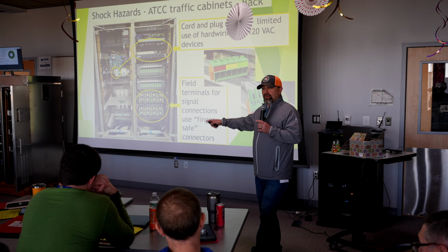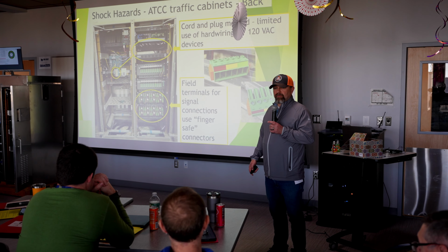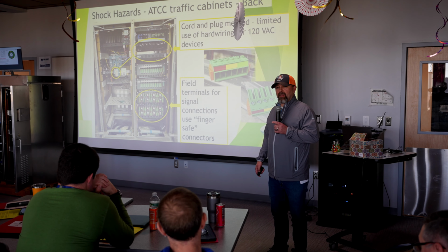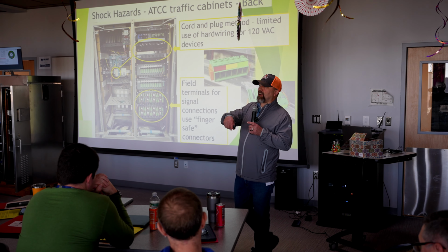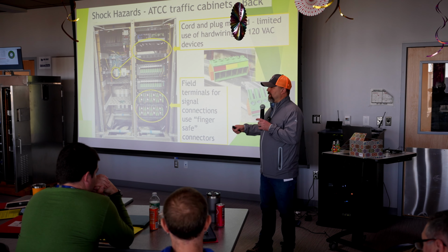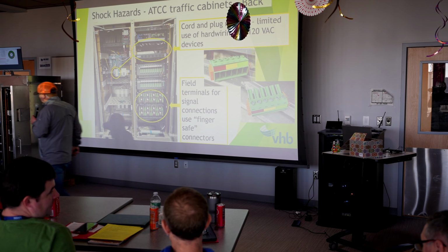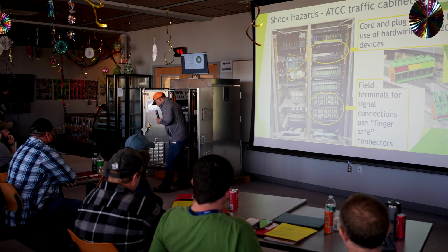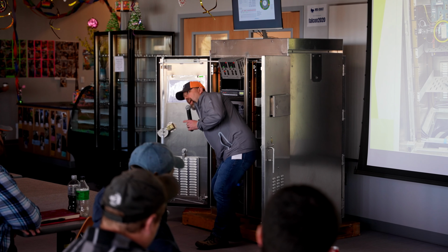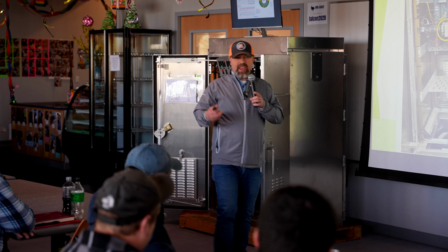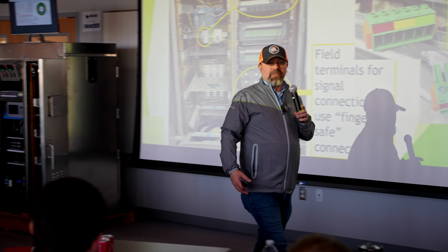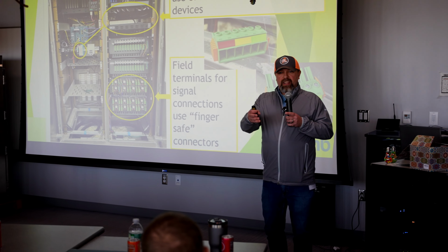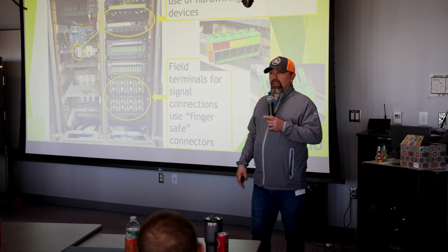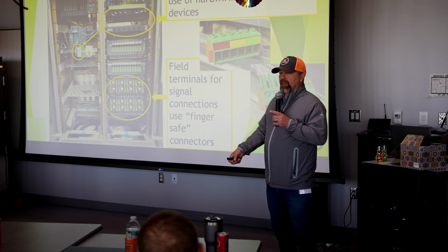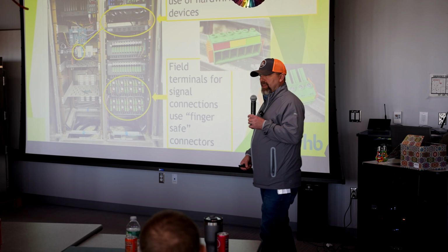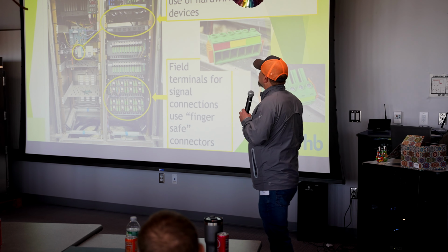Oh, the way the conductors are run through the inside of the cabinet? Really ought to at least be in flex. Mm-hmm. Just to keep that... I'd agree with that. What Eric's talking about is loose conductors being run through the cabinet. And really, if we take a quick look over here, a lot of those loose conductors would be behind the service assembly. And it's not that easy to get to, but yes, if you've got to get down there and start reaching in there, Eric's saying some of the edges are sharp, so you have the potential to chafe those wires. I would agree that at least some woven sleeve, something to keep it so that it can't have rub damage.